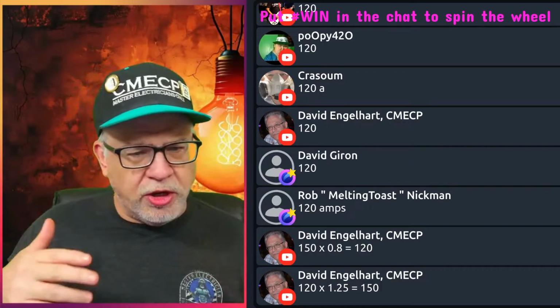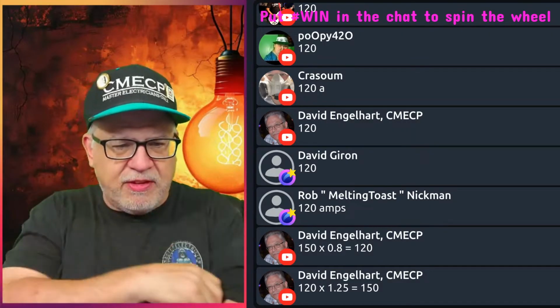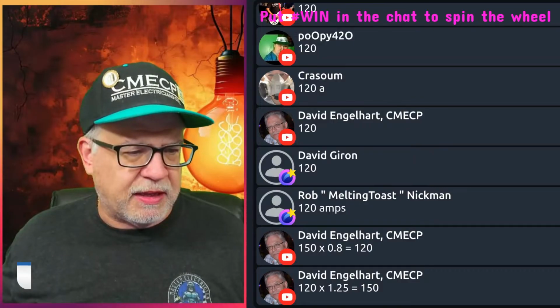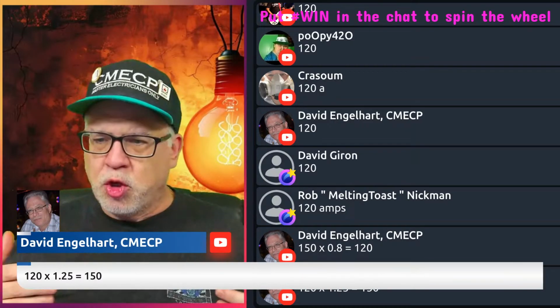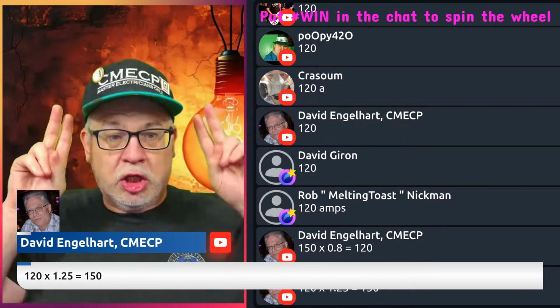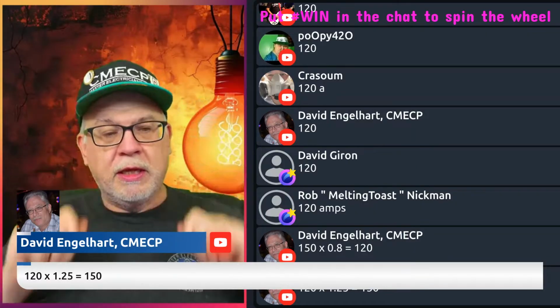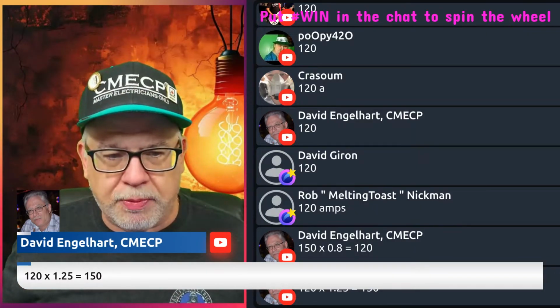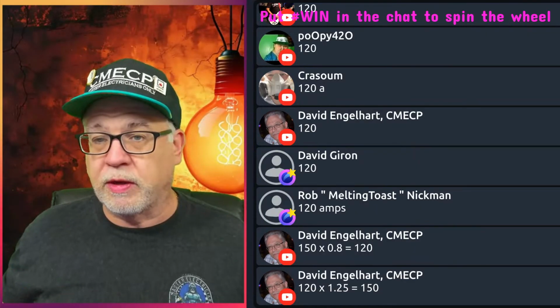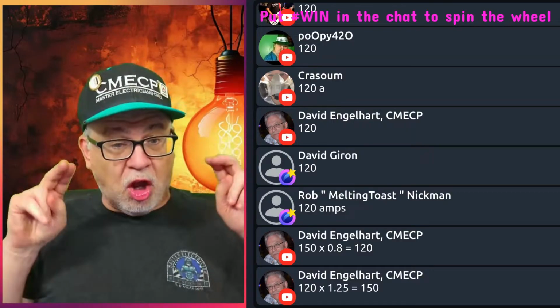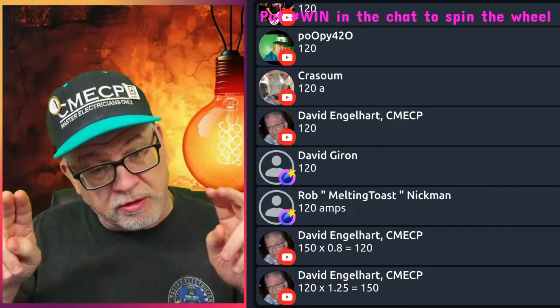So depending on what you're given, like in David's example, if you know it's 120 amps of continuous load, you ask, what breaker do I put it on? Well, you take 120 times 1.25. That's also what you use to size the conductor.